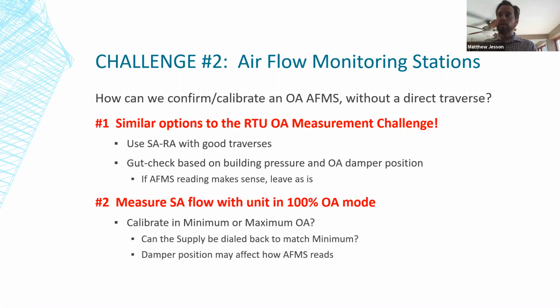And it's also important to note that your damper position might affect how your airflow station reads. Often these airflow stations end up getting installed right inches from the outdoor air damper. And if that damper is just cracked open, that could read very differently from the way it will read when it's fully open. I've also seen an air handling unit with an exhaust air damper or relief, where the airflow station was installed inside the unit just under the exhaust damper. When that damper was fully closed, it would still read airflow because there was turbulence around that airflow station inside the unit. So I think it ended up having to be relocated onto the other side of the damper.